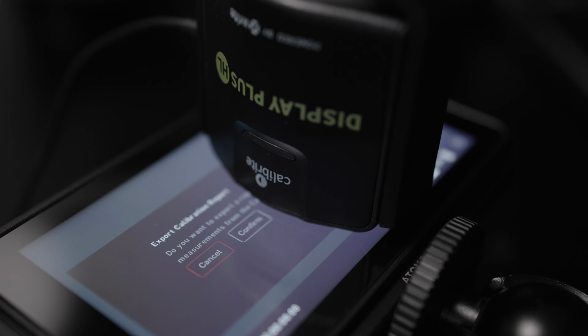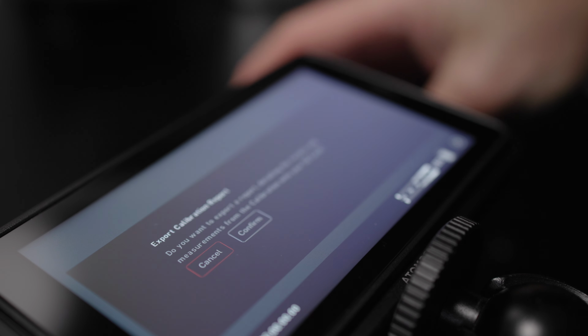It'll then run through a very gentle tonal scale, and the probe will read those, and it will figure out any gamma corrections that need to take place. And once it has all that information, it will generate a calibration LUT. It will write that back into the hardware of the device so that next time it's turned on, it is calibrated and ready to eyeball and trust, which is the important thing about this process.